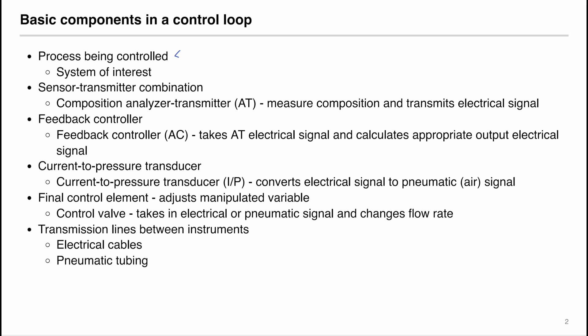First, we need to identify a process that we want to control — that will be the system of our interest. Within the system, we will want to have a sensor-transmitter combination. For example, that could be a composition analyzer that gives us the composition of a liquid. Its input is the composition, and it transmits or outputs an electrical signal. We denote this as AT, where A stands for analysis and T is transmitter, and it usually has the symbol of an AT circle.